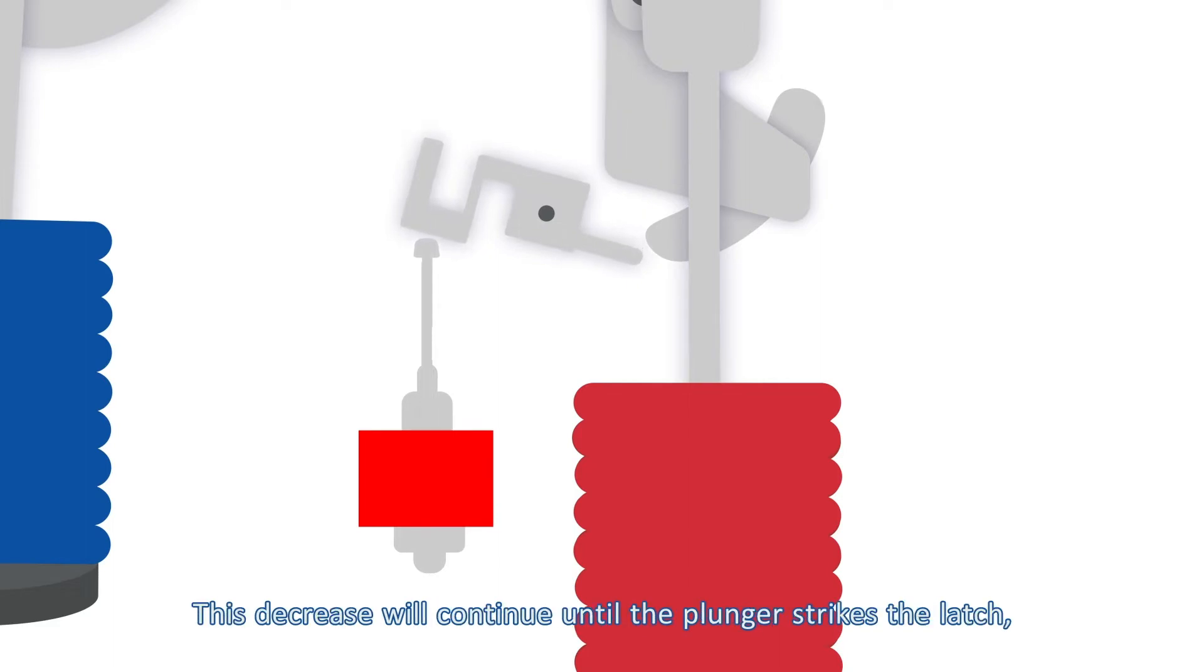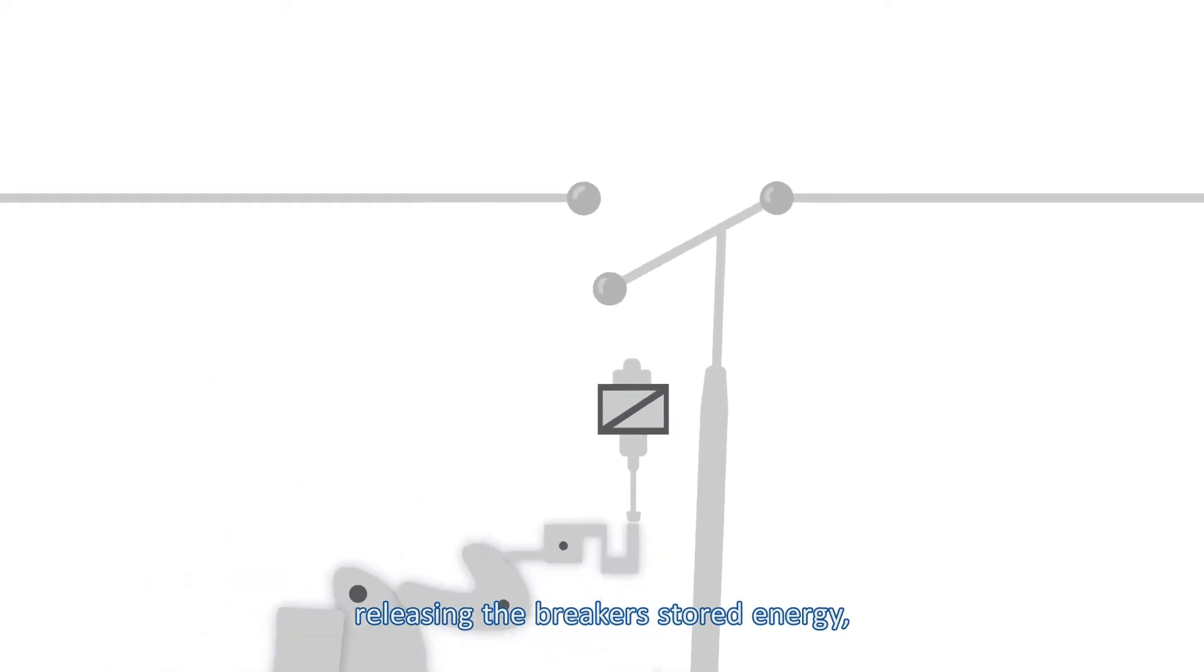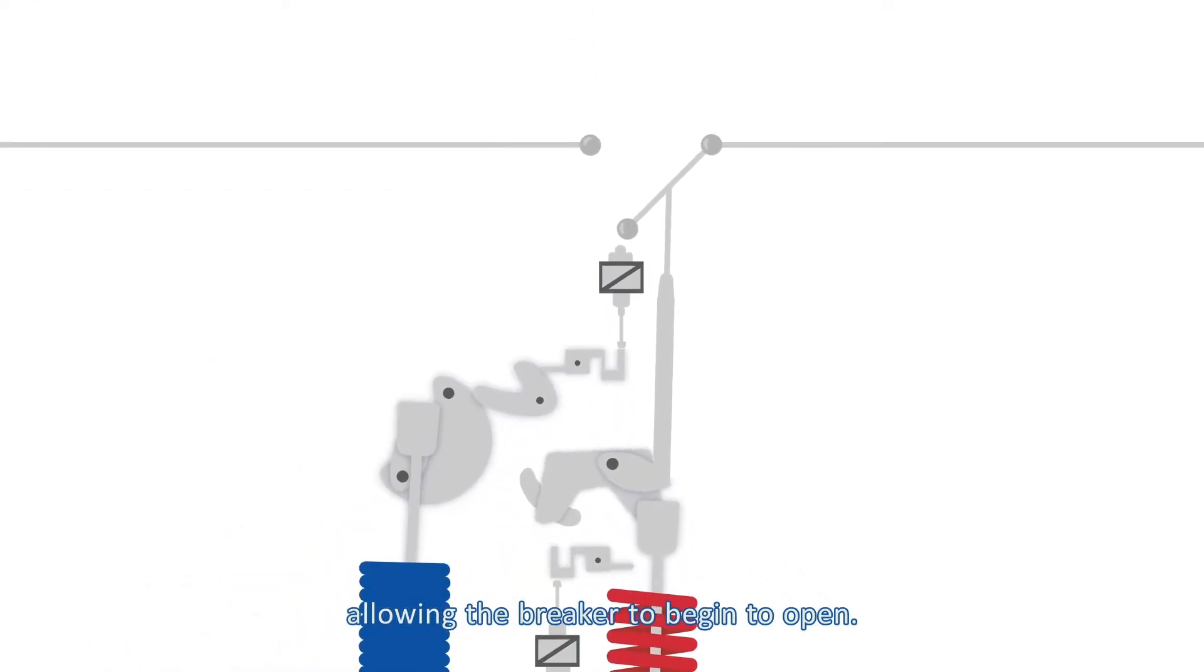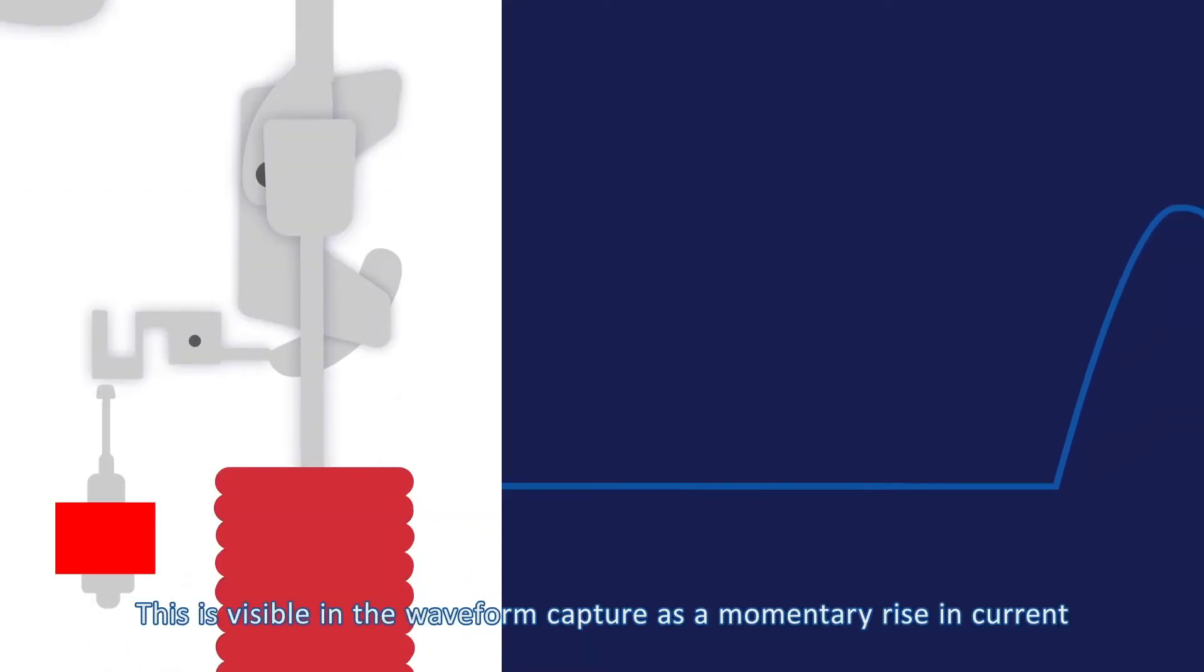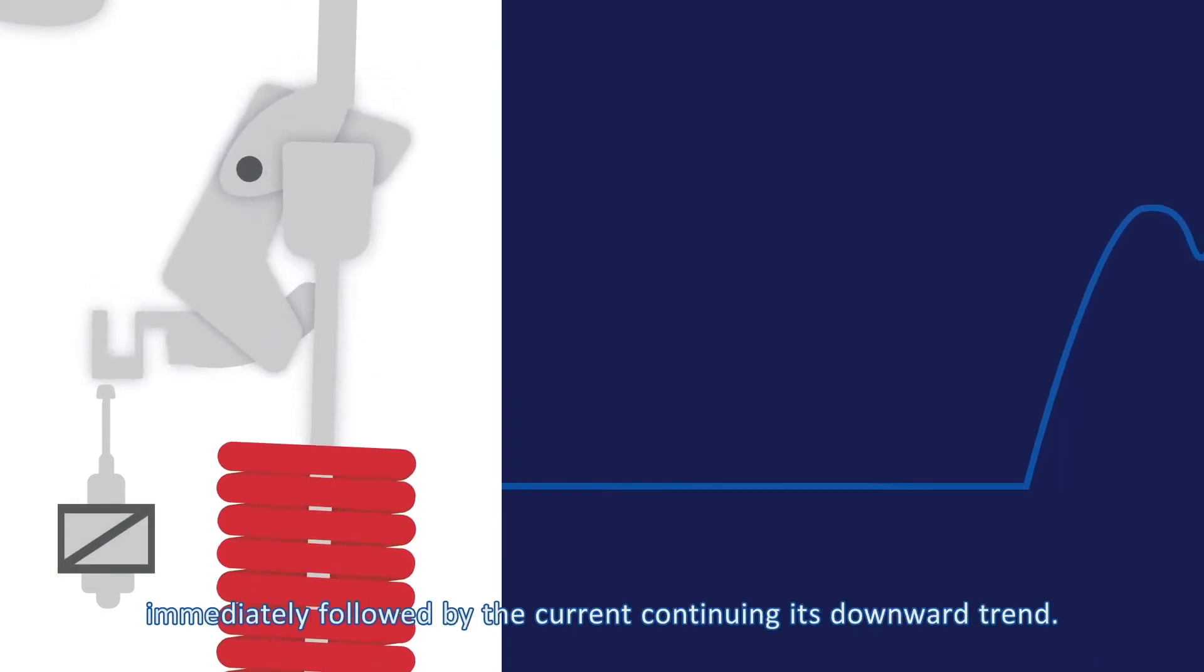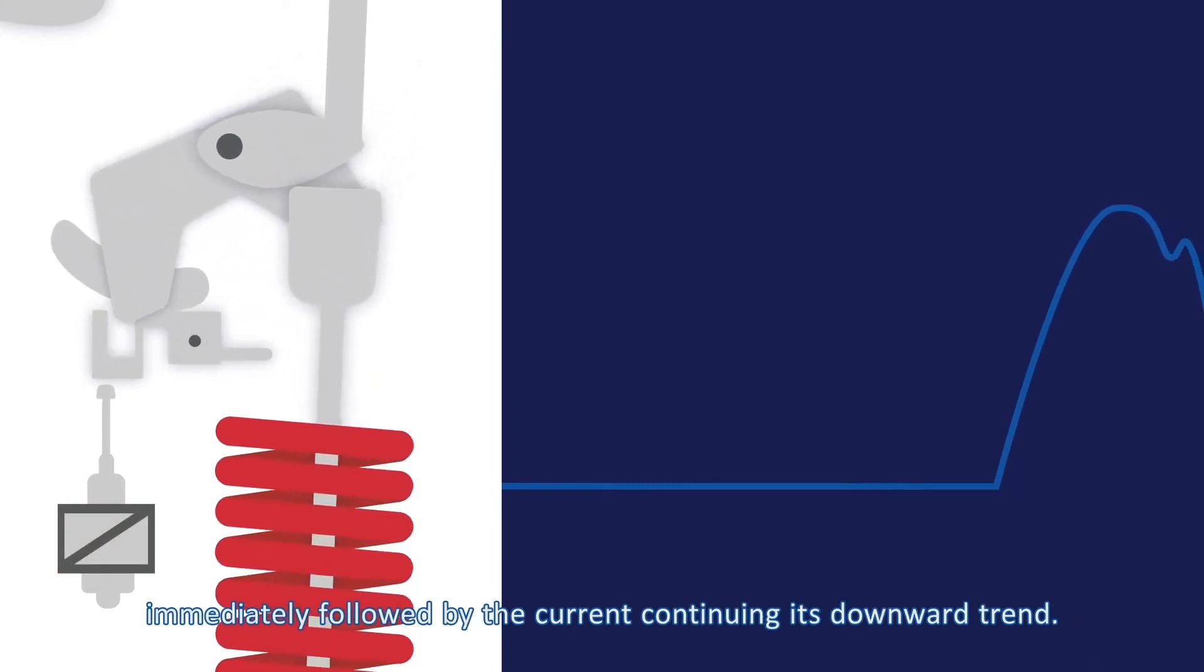This decrease will continue until the plunger strikes the latch, releasing the breaker's stored energy, allowing the breaker to begin to open. This is visible in the waveform capture as a momentary rise in current immediately followed by the current continuing its downward trend.